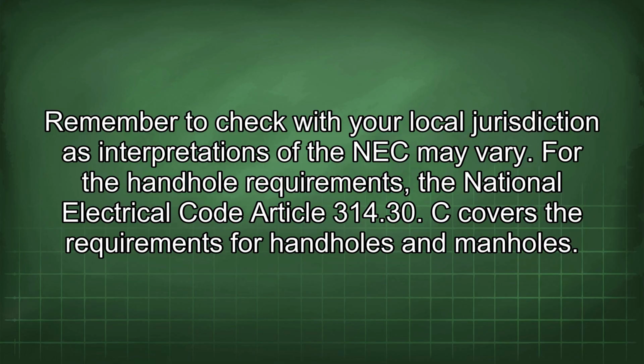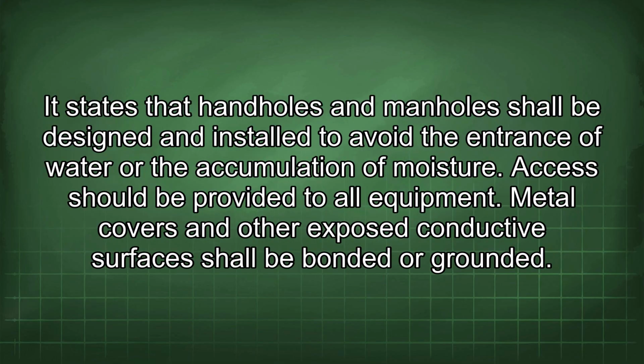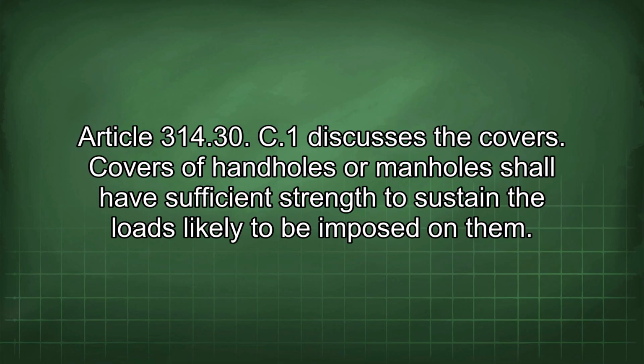For the handhole requirements, the National Electrical Code Article 314.30(C) covers the requirements for handholes and manholes. It states that handholes and manholes shall be designed and installed to avoid the entrance of water or the accumulation of moisture. Access should be provided to all equipment. Metal covers and other exposed conductive surfaces shall be bonded or grounded. Article 314.30(C)(1) discusses the covers. Covers of handholes or manholes shall have sufficient strength to sustain the loads likely to be imposed on them.